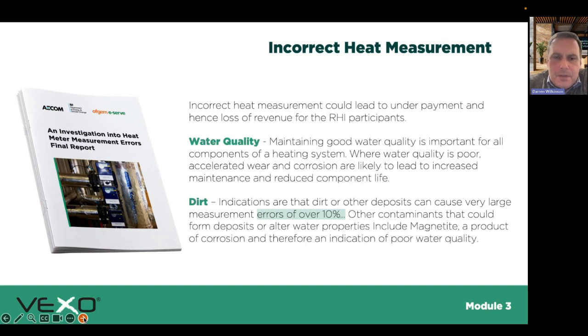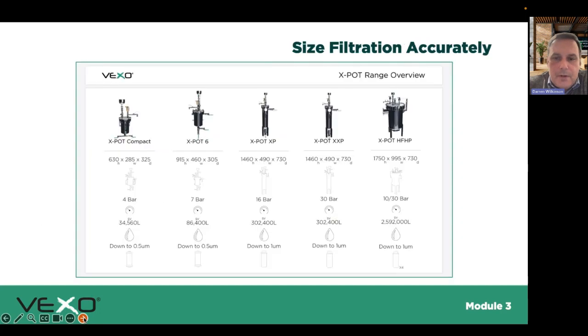There was a big surge, wasn't there, in the renewable heat incentives and biomass, for example, things like that. There's a huge amount of incentives, so a lot of these systems were installed, but certainly a lot of district heating schemes are being installed now, feeding up to HIU units. You will have errors on the heat meters, so the ESCO, whoever's providing the energy, essentially will be potentially losing money. We certainly have some thermal losses anyway that are calculated into a standing charge, but at the meter itself, if you have turbid water, it will throw out the accuracy.